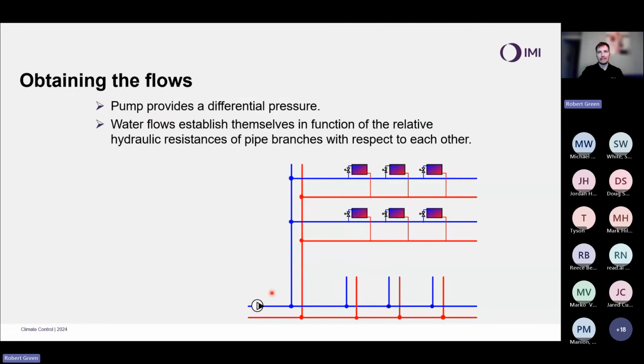water is fundamentally lazy. We have a higher available differential pressure at the inlet of the system than we have towards the extremes of the system. So invariably, we end up with overflows towards the start and underflows towards the end. And that's because, if in this system we had 4 identical risers for the sake of argument, because of my distribution network, we are losing differential pressure in my piping.